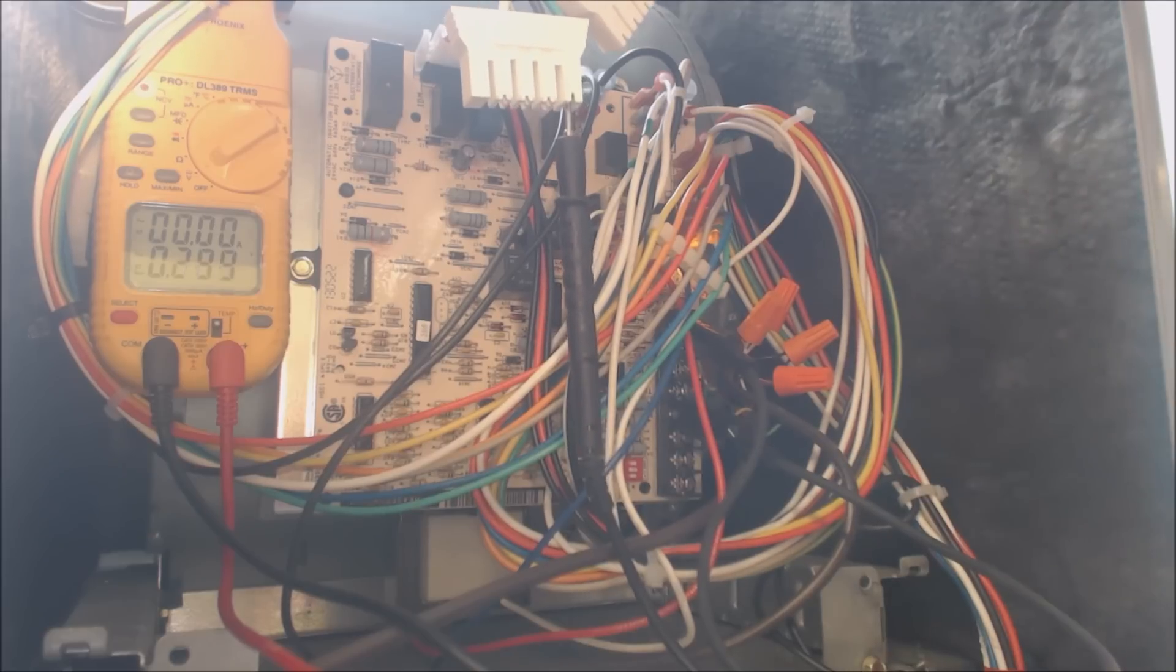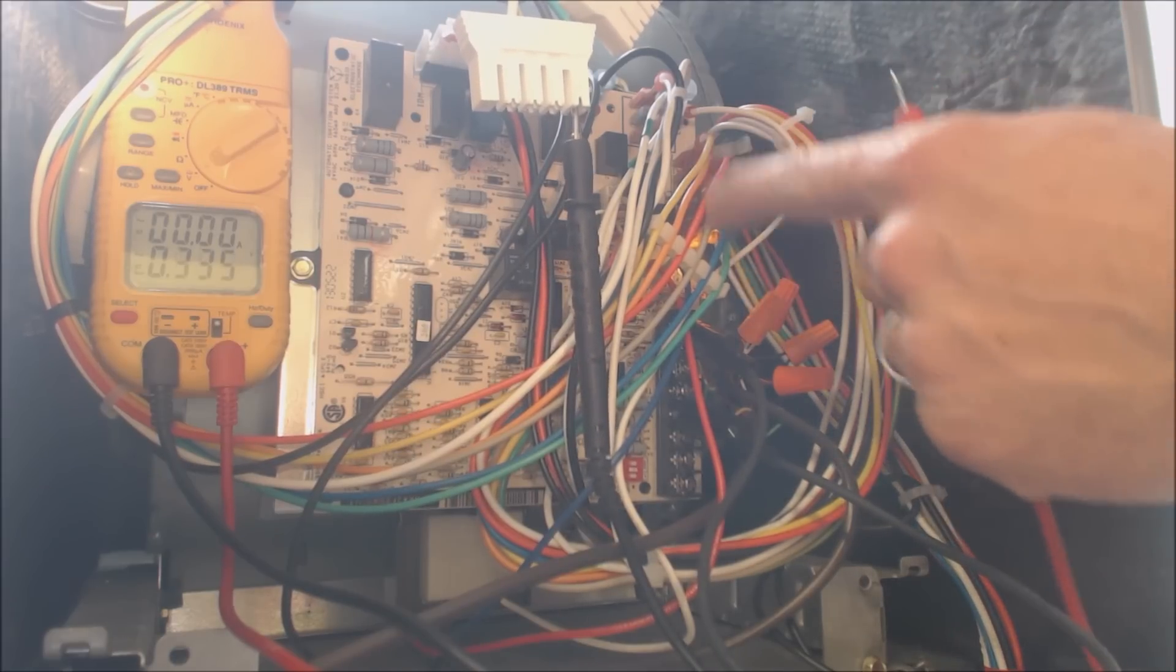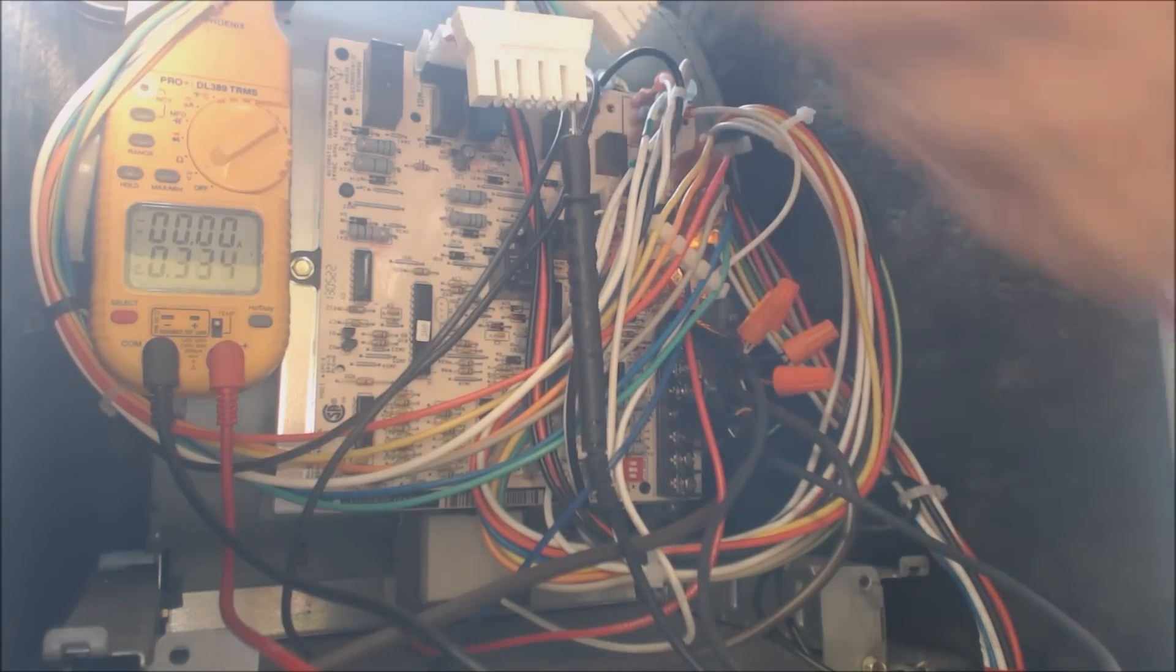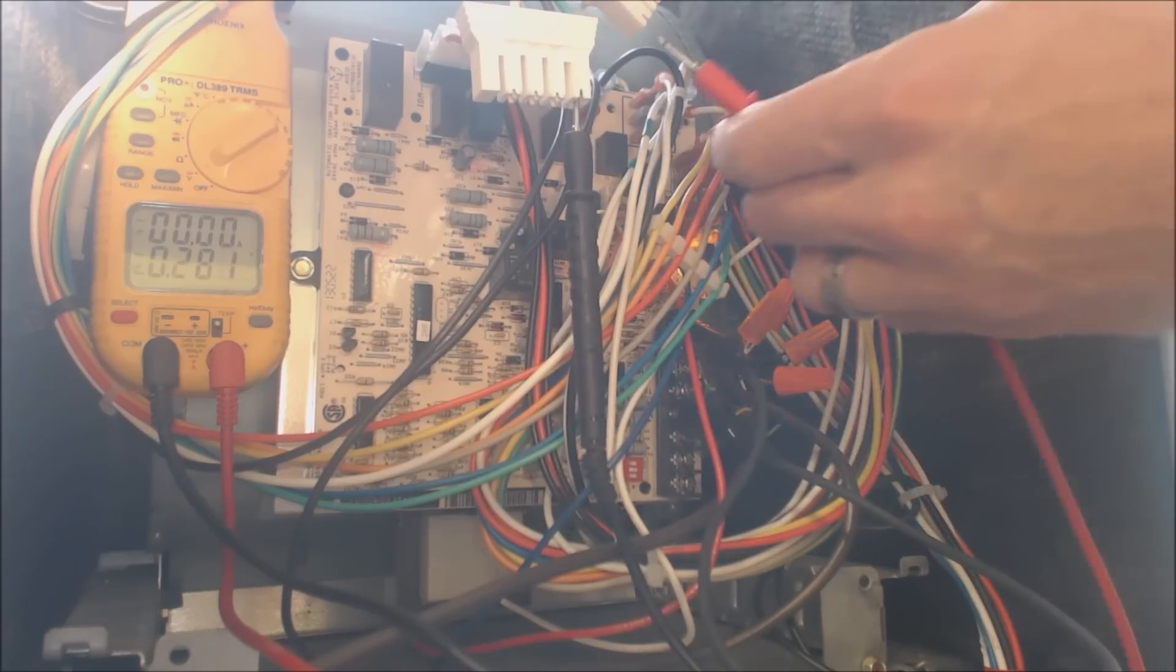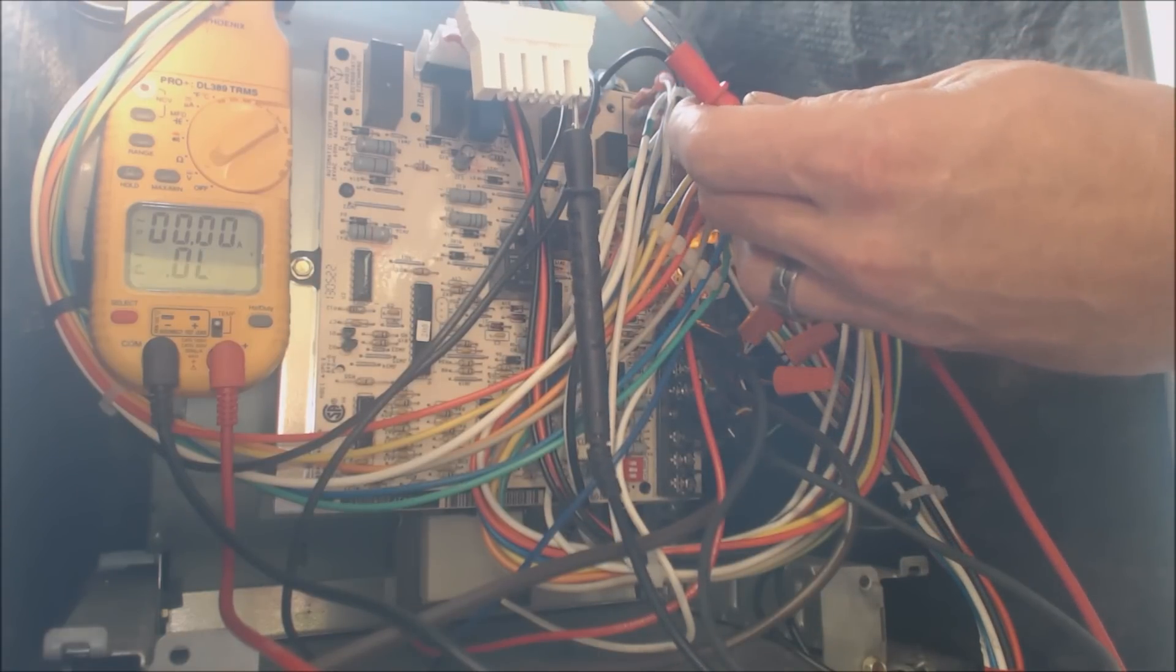But every manufacturer is going to be different when they program which one they're going to be sending the voltage to the X13 blower motor with. In this case, we do read 27 volts.